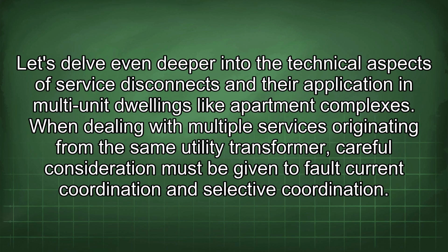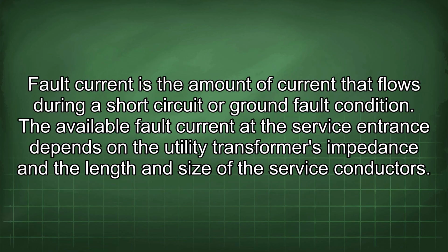Let's delve even deeper into the technical aspects of service disconnects and their application in multi-unit dwellings like apartment complexes. When dealing with multiple services originating from the same utility transformer, careful consideration must be given to fault current coordination and selective coordination. Fault current is the amount of current that flows during a short circuit or ground fault condition.